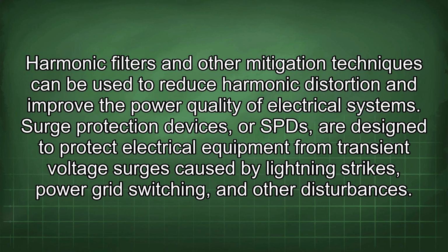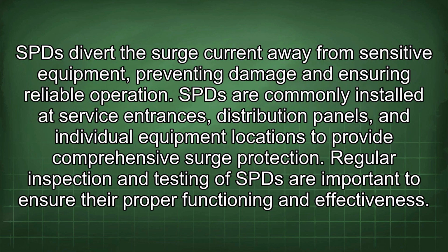systems. Surge protection devices, or SPDs, are designed to protect electrical equipment from transient voltage surges caused by lightning strikes, power grid switching, and other disturbances. SPDs divert the surge current away from sensitive equipment, preventing damage and ensuring reliable operation. SPDs are commonly installed at service entrances, distribution panels, and individual equipment locations to provide comprehensive surge protection. Regular inspection and testing of SPDs are important to ensure their proper functioning and effectiveness.